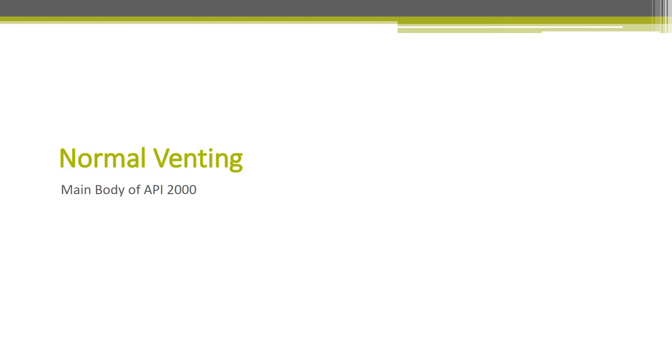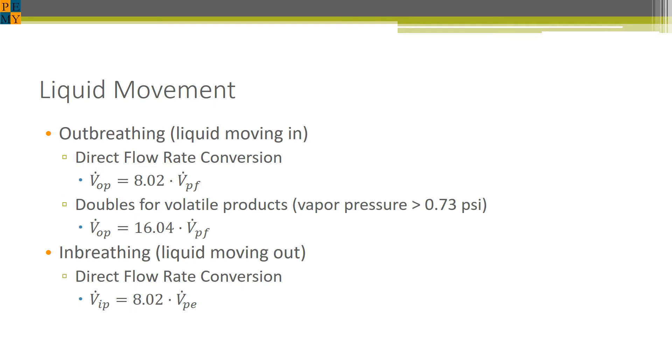Normal venting. Let's begin with normal venting for API 2000. Here we consider the effects on normal venting through liquid movement. When product is getting pumped into the tank, it generates vapors which need to be alleviated, outbreathing. This equation is a direct flow rate conversion. Essentially, the amount of flow coming into the tank must be the same amount of flow rate coming out of the tank. 8.02 is merely a factor that accounts for unit conversion.